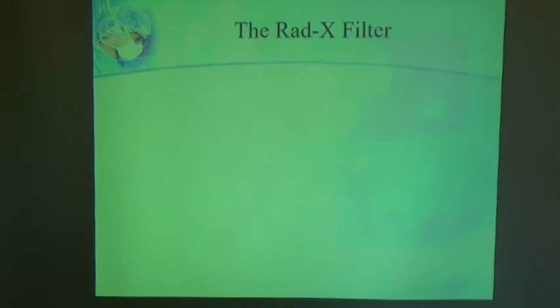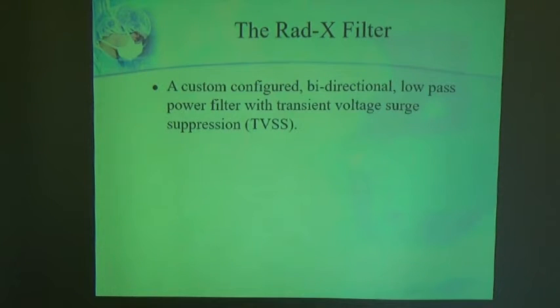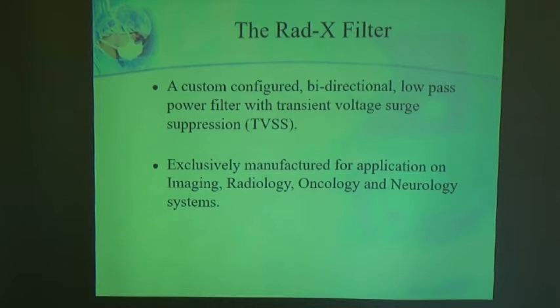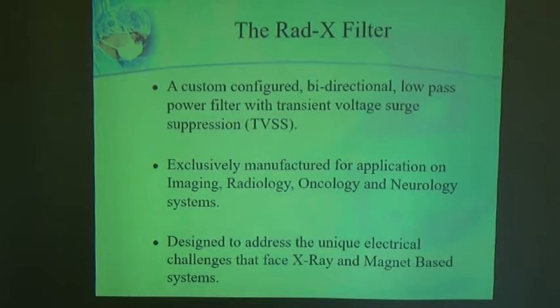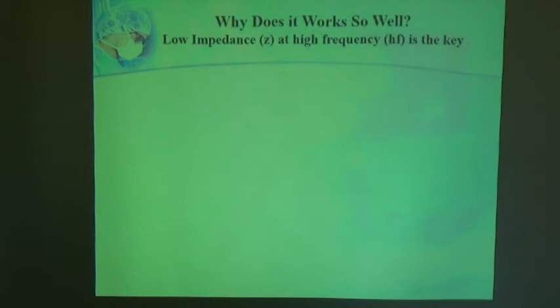The Rad-X filter, a custom configured bidirectional low pass power filter with transient voltage surge suppression. It is exclusively manufactured for application on imaging, radiology, oncology, and neurology systems. Designed to address the unique electrical challenges that face X-ray and magnet-based systems. Why does it work so well? Low impedance at high frequency is the key.